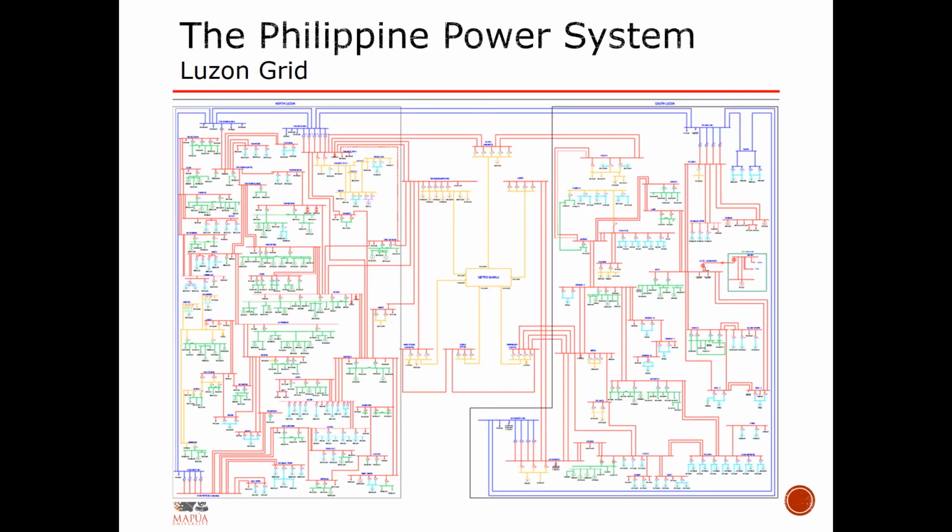The Luzon Grid looks like this right now. The Luzon Grid is composed of a majority of 230 kV transmission system, but its backbone, the voltage level that delivers the bulk or majority of the power, is the 500 kV lines. Eventually, those are delivered to distribution utilities or electric cooperatives that have voltage levels at 69 kV.